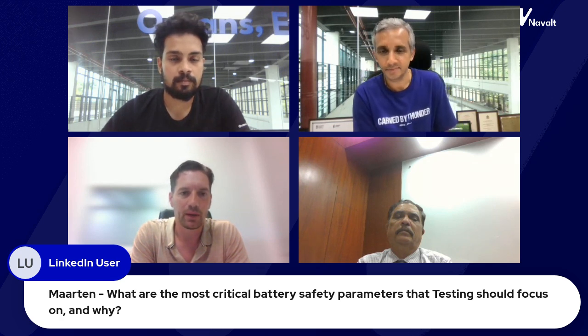The main challenge is in the battery construction itself. Is your wiring up to all the currents that are running? How about your fuses? Did you take into account the short circuit currents that could run? Because if you short circuit the cell, very high currents can run through your system, and is your fuse capable of handling this?